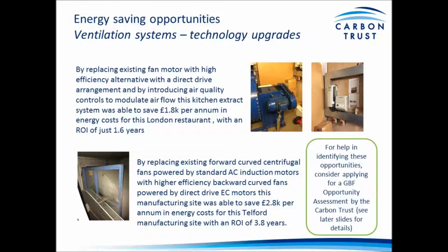If you are looking to upgrade your ventilation systems, I've given a couple of examples here of recommendations we have seen and made. The first example, shown at the top, is a kitchen extract fan, which had its motors upgraded to a higher efficiency alternative, but its configuration had also been changed to reduce friction losses from the existing belt and pulley arrangement that can be seen in the image, to a direct drive system, so the motor is directly connected to the fan rather than via a belt and pulley.